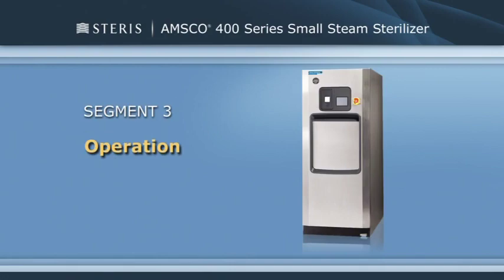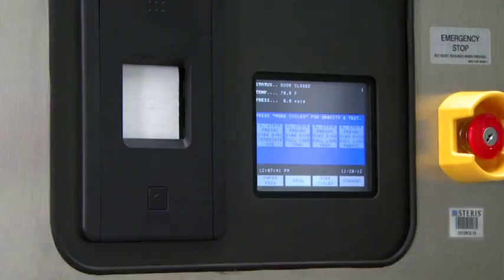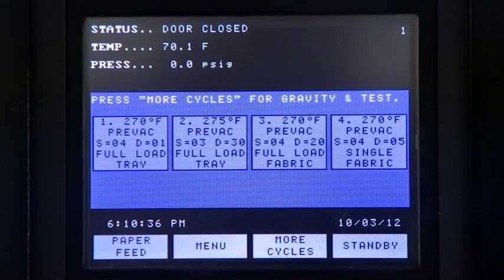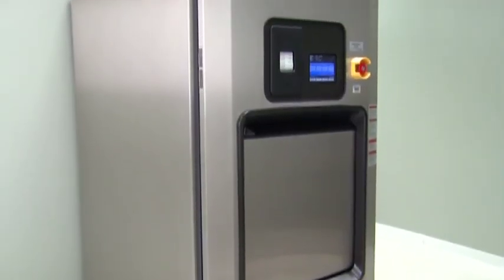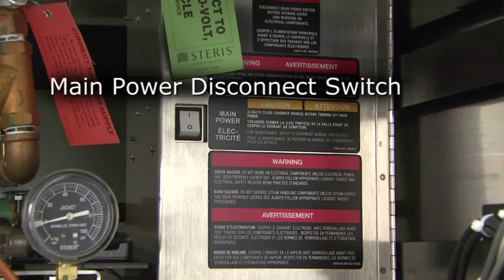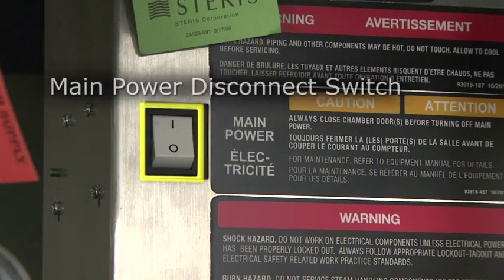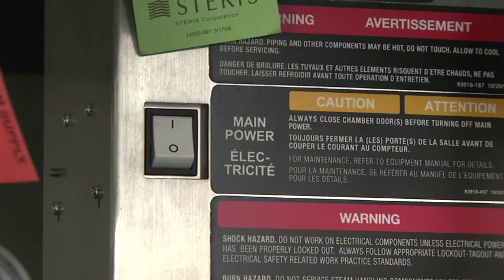The controls for the sterilizer are contained within the control touchscreen. Control touchpads appear on the screen as needed during each operation. Available controls change as the sterilizer steps through different operations. Let's take a look at the main sterilizer and cycle controls. The main power disconnect switch is located at the side of the sterilizer on the main control box. This switch disconnects power to the control. Under normal operation, this switch is left in the on position at all times and accessed only when servicing the sterilizer.